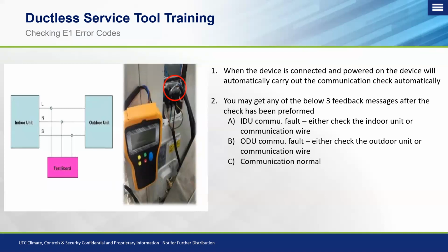Finally, your communication is normal. So if you have a scenario where you know you have a documented E1 code, the indoor unit's displaying an E1, the system's displaying an E1, and you get a communication normal, if that happens, that indoor PCB is faulty and will need to be replaced. Of course, in a multi-zone, you want to check individual zones on there to make sure that you know which one is coming back as communication normal and which indoor PCB may or may not be faulty.